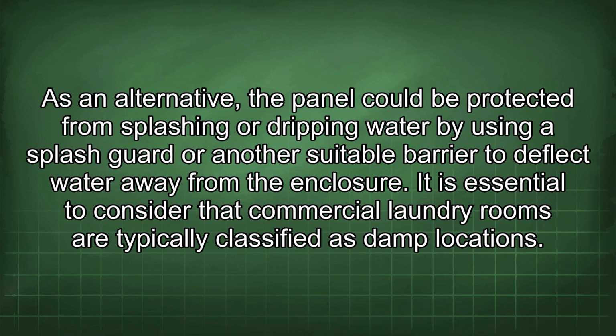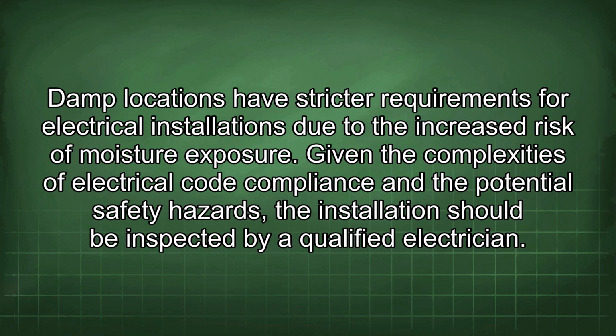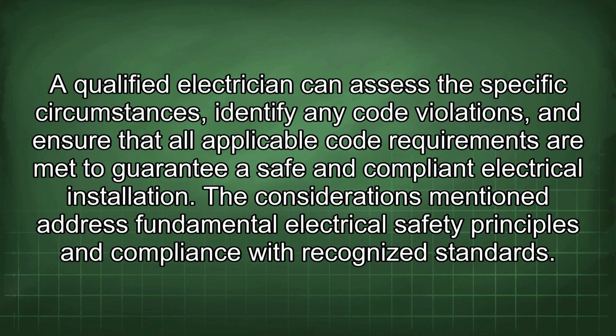It is essential to consider that commercial laundry rooms are typically classified as damp locations. Damp locations have stricter requirements for electrical installations due to the increased risk of moisture exposure. Given the complexities of electrical code compliance and the potential safety hazards, the installation should be inspected by a qualified electrician. A qualified electrician can assess the specific circumstances, identify any code violations, and ensure that all applicable code requirements are met to guarantee a safe and compliant electrical installation.